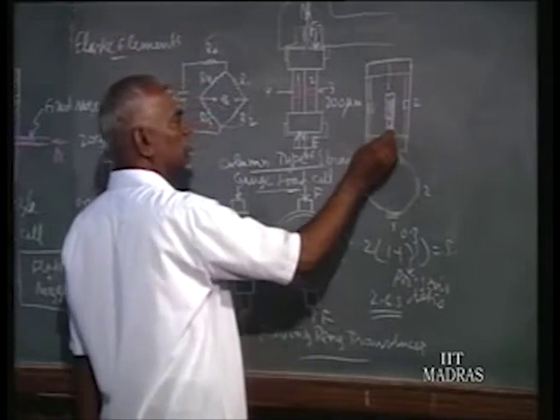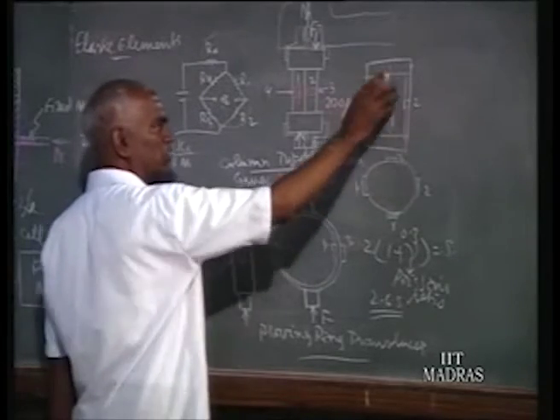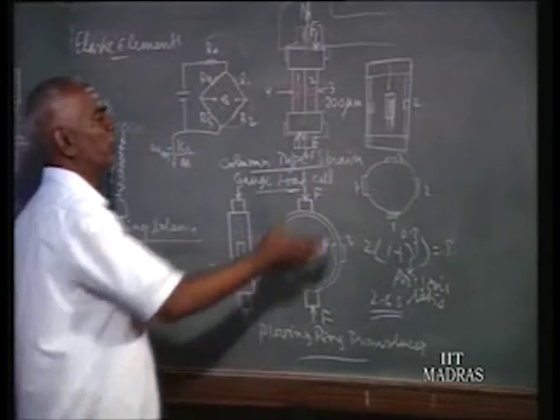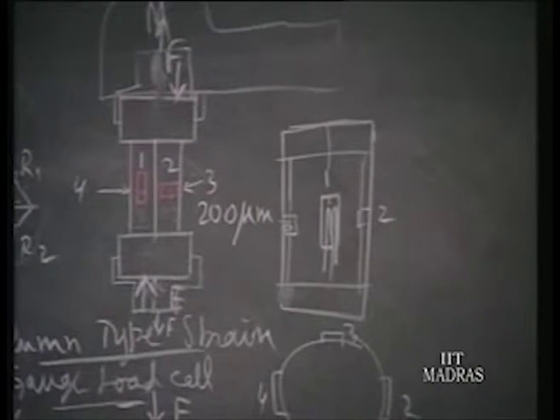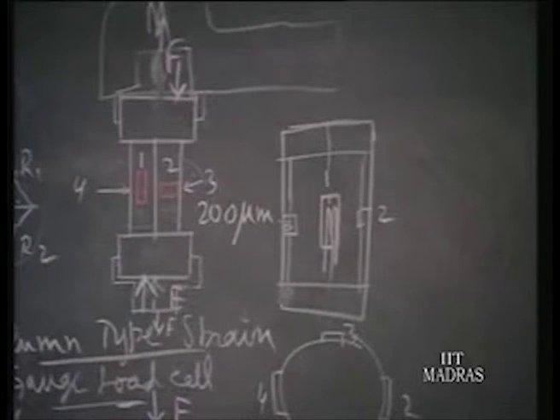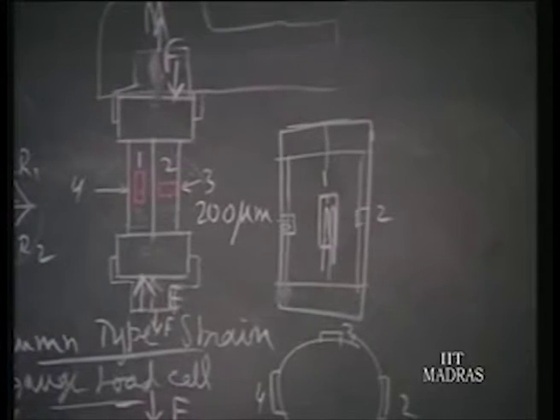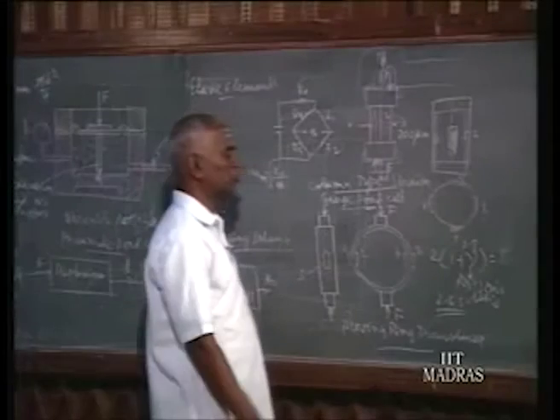Have the hollow constructions, small wall thickness, so inside it will be hollow, so that you find it is weak, at the same time sufficient area is there for fixing the strain gauges. So all these measures we can observe, so that sufficient sensitivity comes. But another better design is going for the proving ring transducer.